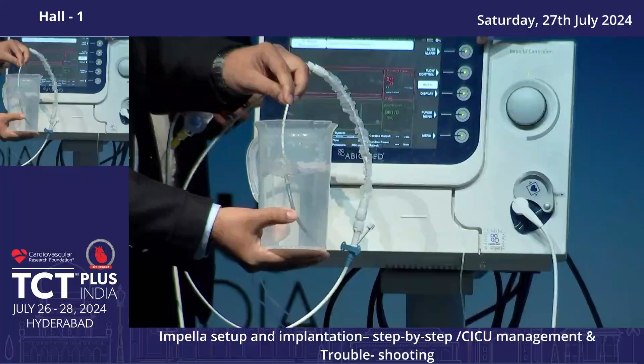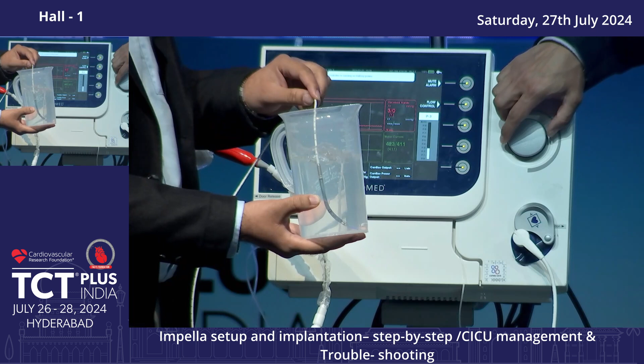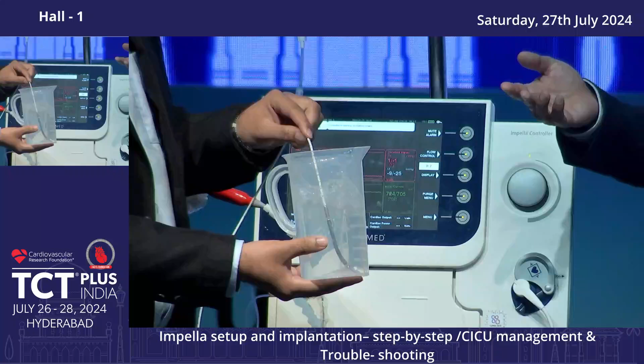I'm just going to turn the flow control down before it gets too high. Okay? So these buttons on the device are the way you actually adjust flow control. Flow control is marked by a button called flow control. Okay? So you press the flow control button if you need to turn it up, and you turn this knob to select the P level that you want, and you press the knob in, and you'll see that the amount of flow that the device provides starts to go up. Generally speaking, in high-risk PCI, we'll leave it on P9, or we'll leave it on auto, and then when it comes down back into the ICU, you'll end up leaving it on P9 for most of the time.